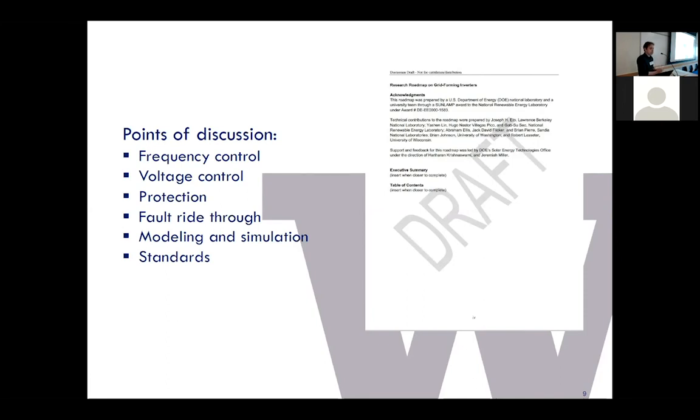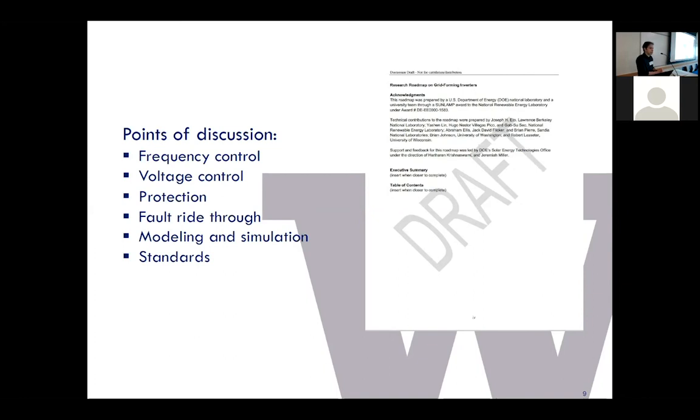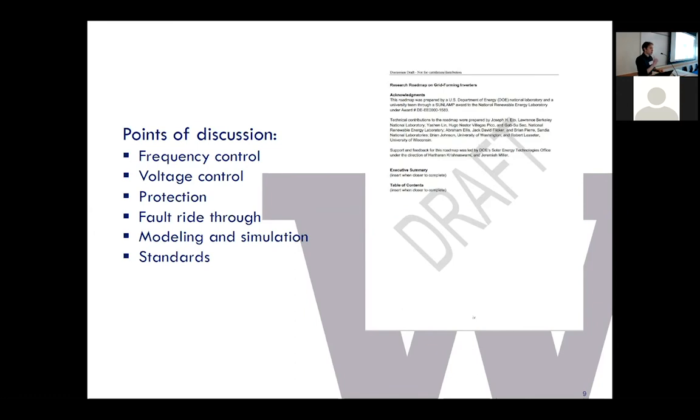We discuss frequency control, voltage control. Protection is a big issue too. In the current setting if you have a fault on a system you can rely on large synchronous machines to provide relatively large short circuit currents to trip off protection. It turns out that with power electronics and the semiconductor devices that are used to create them, they cannot handle large over currents and so we have to rethink how fault ride through is done. This is particularly important for grid forming inverters because they act like voltage sources. If you short a voltage source obviously it's going to provide a massive amount of current but the power electronics can't provide very large amounts of currents for extended periods without damaging those converters. We have to rethink how fault ride through is done with these new types of controllers.